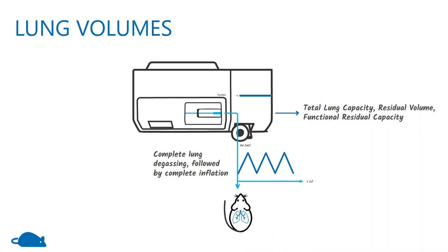In the lung volumes measurement, the lungs are completely degassed after ventilating with pure oxygen and then reinflated back to total lung capacity. The flexi-vent then calculates the total lung capacity, residual volume, and functional residual capacity.